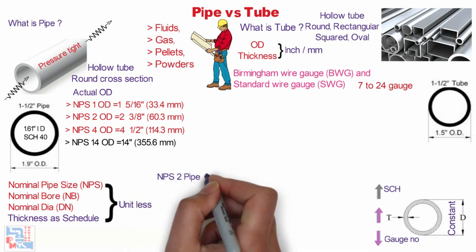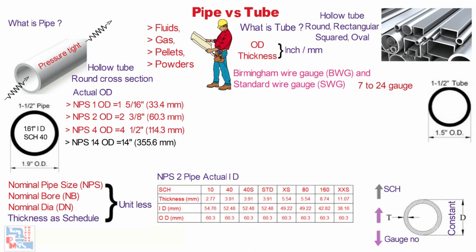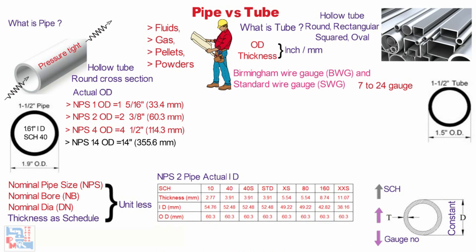Now let's see the actual inside diameters of a 2 inch pipe. For different schedules, there are different thicknesses which give different IDs for a 2 inch pipe. For schedule 10, pipe thickness is 2.77 mm, giving an ID of 54.76 mm for an OD of 60.3 mm. For schedule standard, thickness is 3.91 mm, giving an ID of 52.48 mm with OD of 60.3 mm — which is fixed. For schedule 160, the thickness is 8.74 mm, giving an ID of 42.82 mm with OD of 60.3 mm.